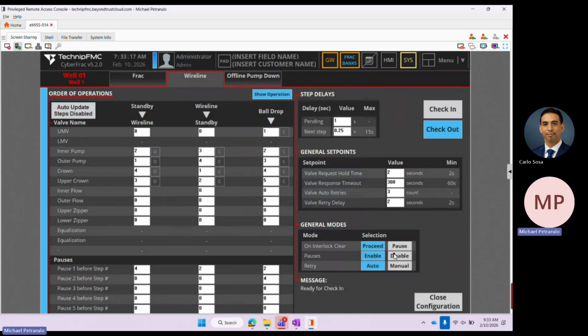So that's where this does come in, because hydraulics is still going to be a thing. Say in the dead of winter you're using half inch hoses, you may need to adjust your valve response timeout because you need the sequencer to understand this valve is going to take 2 minutes. You don't want it to flag it because you know it's traveling, just hang out. Because if it flags it, it goes through this retry protocol and it just gets really annoying.